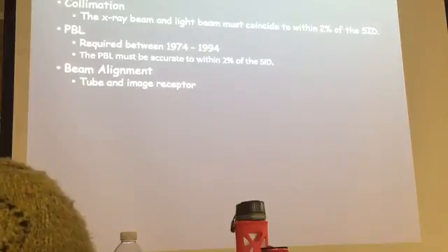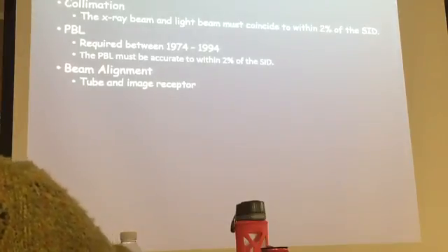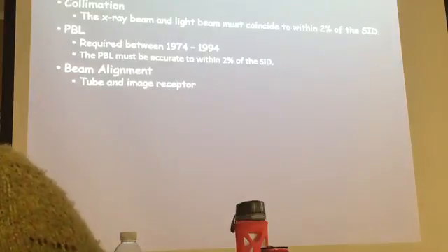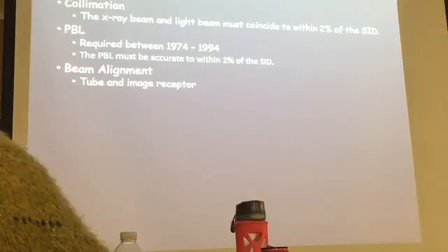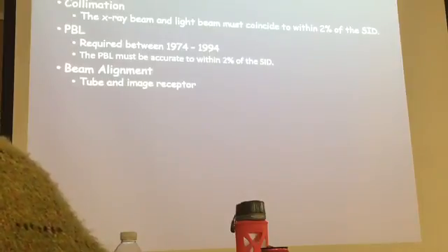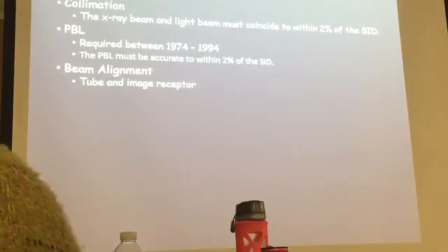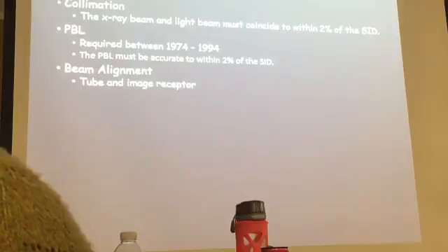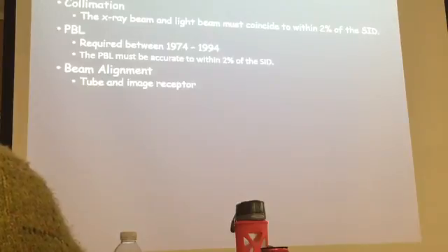Make sense? Christine? So for the positive beam limitation, it's not required anymore, but if they do have it, it's still tested. Yeah. But it's not required anymore for manufacturers to include it, especially with DR. You indicate the size that you want, and the field will open up to that size. See what I'm saying? Because you don't have plates anymore.